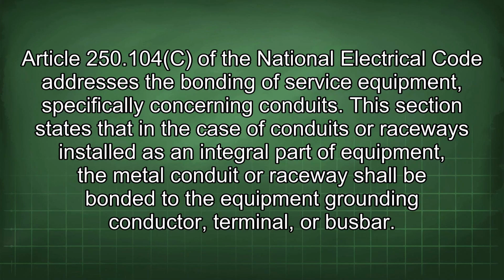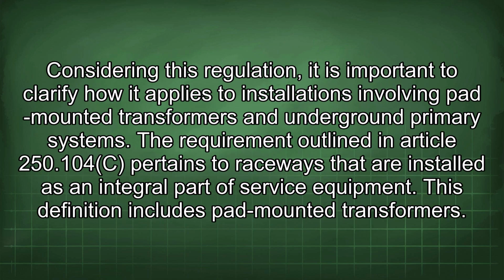250.104(C) of the National Electrical Code addresses the bonding of service equipment, specifically concerning conduits. This section states that in the case of conduits or raceways installed as an integral part of equipment, the metal conduit or raceway shall be bonded to the equipment grounding conductor, terminal, or busbar. Considering this regulation, it is important to clarify how it applies to installations involving pad-mounted transformers and underground primary systems.